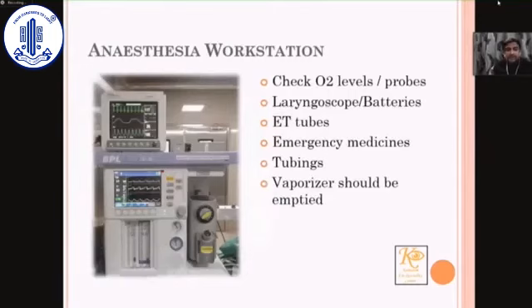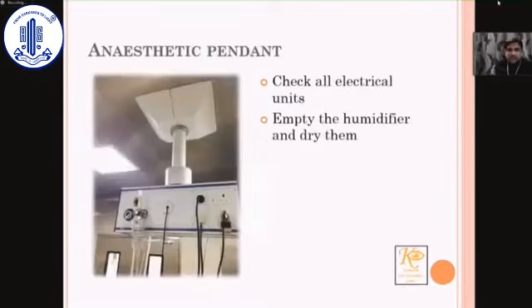The anesthesia workstation, if you have one: check the oxygen levels on a daily basis, as it is an emergency requirement, and oxygen should be available even during your shutdown period. Ensure that the batteries and all the electronic devices are removed, including the laryngoscope. Ensure that all the medicines in your cart are always available even during periods of shutdown. The vaporizer, if you have one, make sure you empty it if you're not planning to use it for more than a week. Otherwise, there's nothing much to talk about the anesthetic workstation.